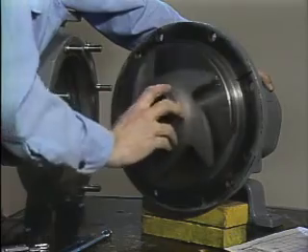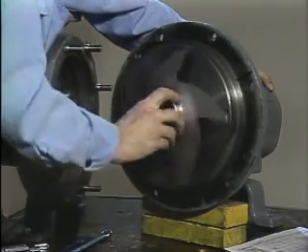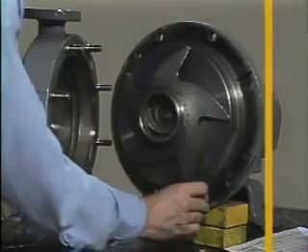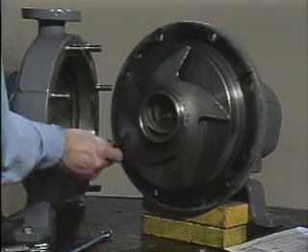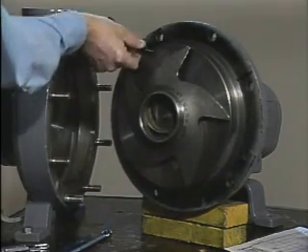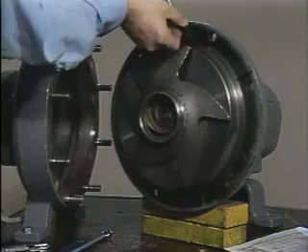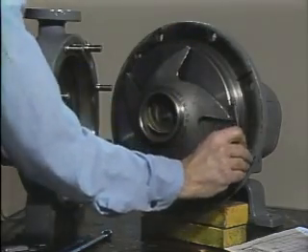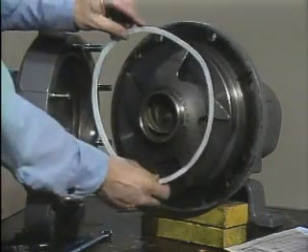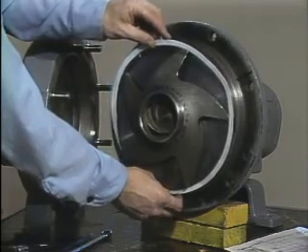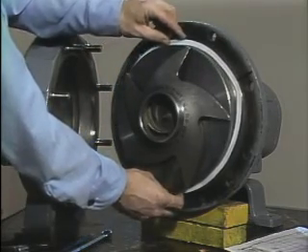After the rotating element is in place, the impeller is installed and tightened. Then impeller clearance is checked and compared with the manufacturer's specifications to be sure that the components have been installed correctly. Once that's done, the seal installation is complete and the pump is ready to be reassembled so it can be returned to service.